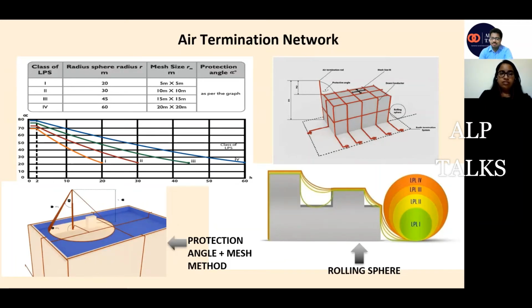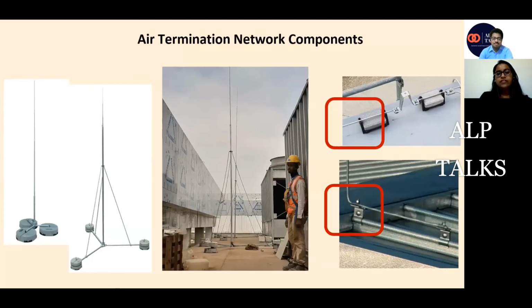There is a difference in how we select the method for our design. Generally, for smooth roofs where there is no human movement, we use the mesh method. Otherwise, we go for the protection angle or, majorly, the rolling sphere method. These types of air terminals are installed over the roof for protection from lightning strikes. The material generally used is aluminium because it is light in weight, easy to install, and cost effective also.